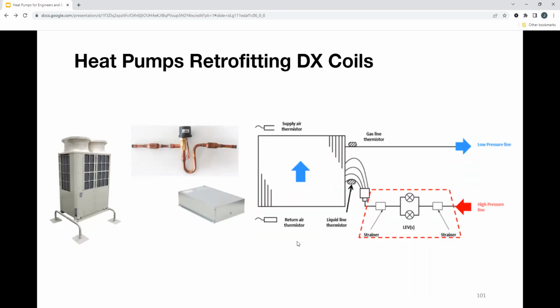Part of this is, you size your coil correctly, and you can control to either discharge temperature, if you are bringing your air down to 55 degrees and then adding a reheat, or you could provide an air handling unit that's feeding a gym and provide cooling and heating based on room air temperature. So you'd have a local controller in that space.